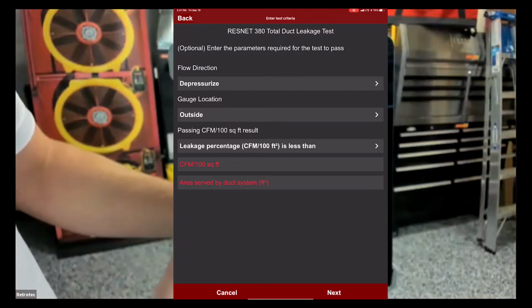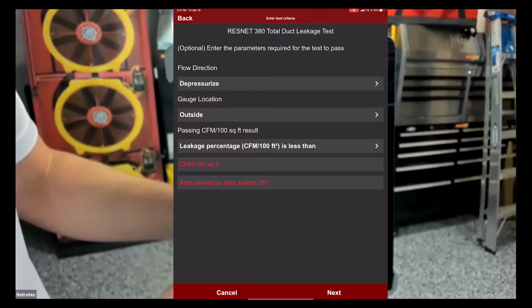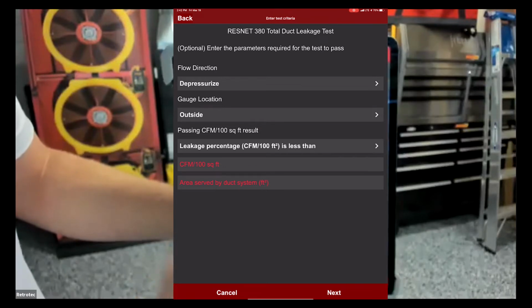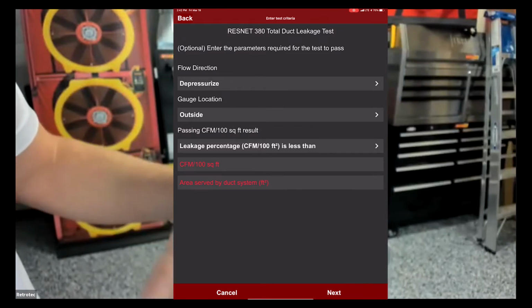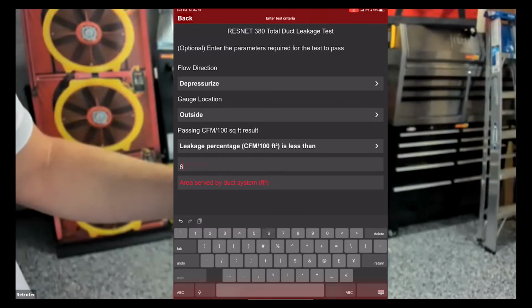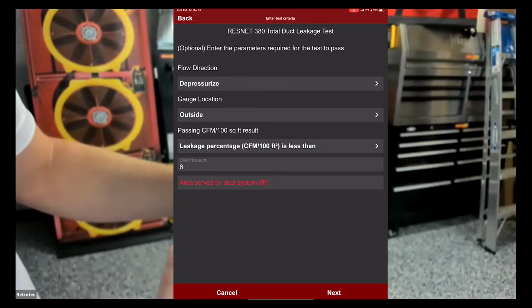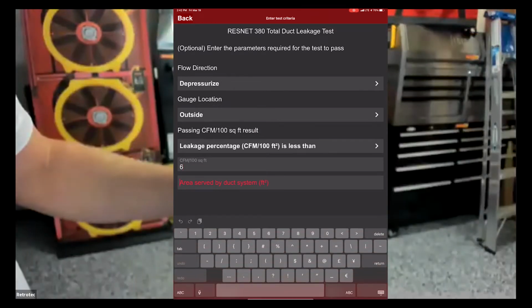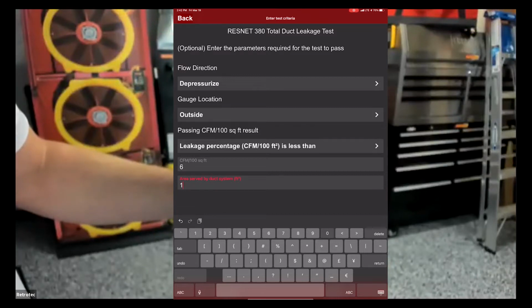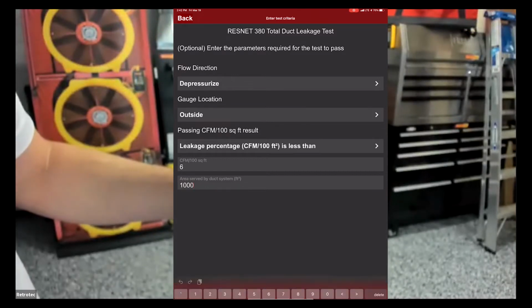So we have that, this is where you can choose. This next option is where you can choose your leakage percentage. I want it less than or equal to CFM per 100 square feet. We'll use our 6 again. And the area served by the system, we'll use the same parameters we did for our manual test, and we'll say 1,000. Then we can hit next.